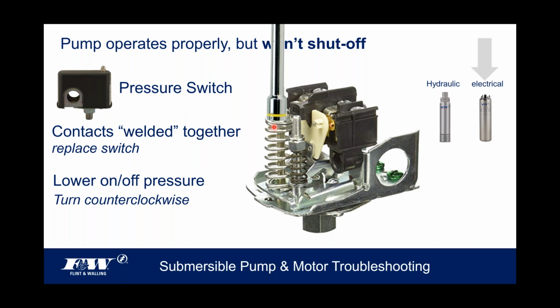Sometimes that's going to be an indication of a pump that is quite a ways along in its life cycle and is starting to lose some performance, a lot of times in the pressure that it can generate. Again, I don't know that this would be a long-term solution, but lowering the pressure on the pressure switch may very well get that pump to shut off at least. And then we can make some decisions after that. They say, hey, we don't like the pressure it's at now. Well, then we've got a choice to make. You want to have higher pressure?